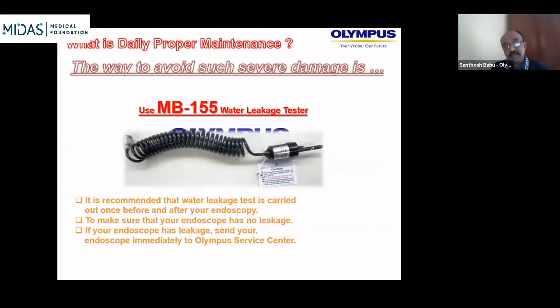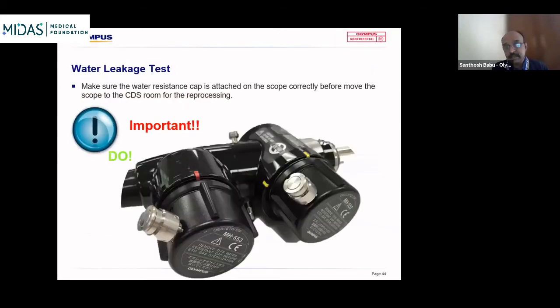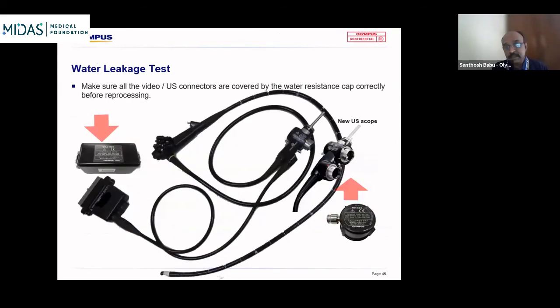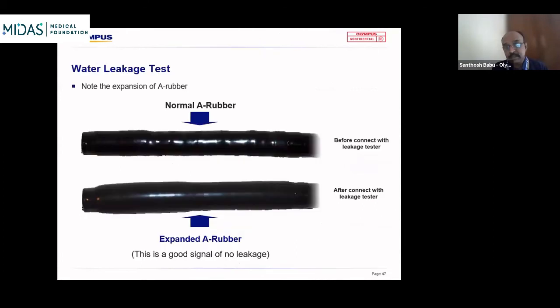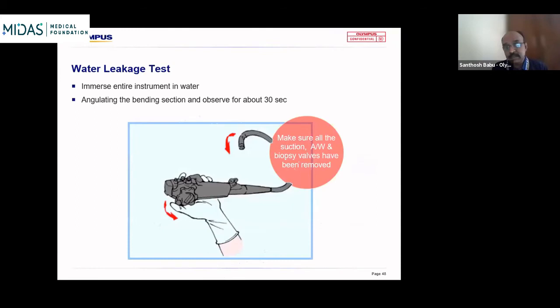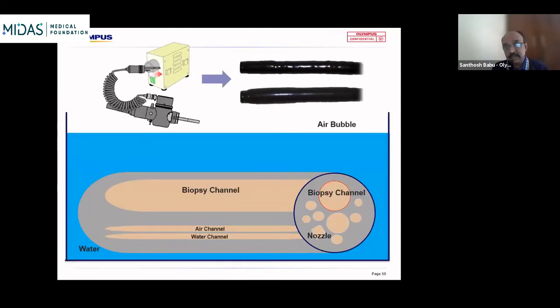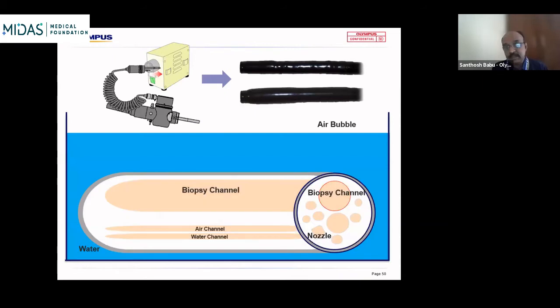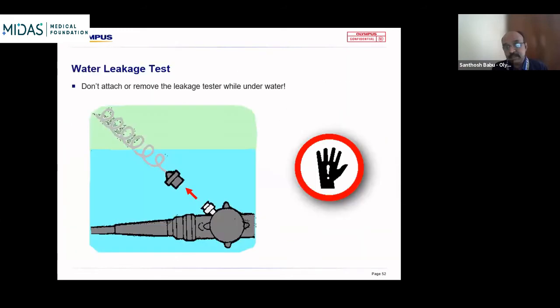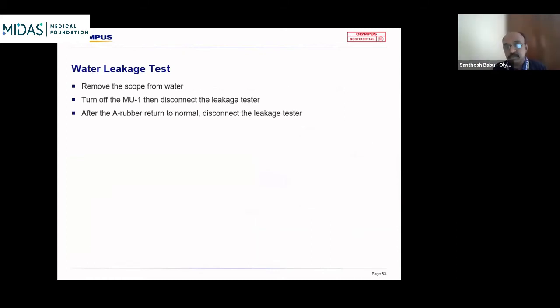For the leak test, you need to attach these water resistant caps. Some scopes come with the cable attached, so they have a different type of connection. Then come into the wash area. The first thing you do is start off with the leak test. The entire scope is sealed, and the spaces between the components are filled with air, so in case there's any leak in the scope, it's visible. If it's in the biopsy channel, bubbles come out. Never ever connect or disconnect the leakage tester while in water.